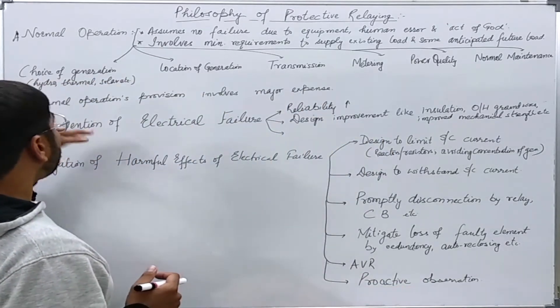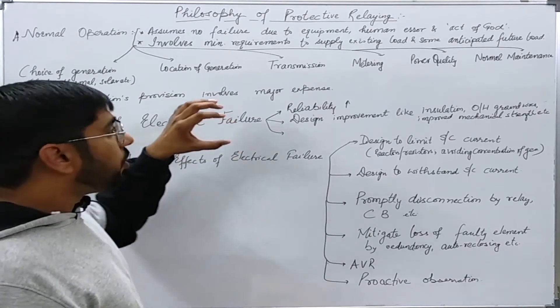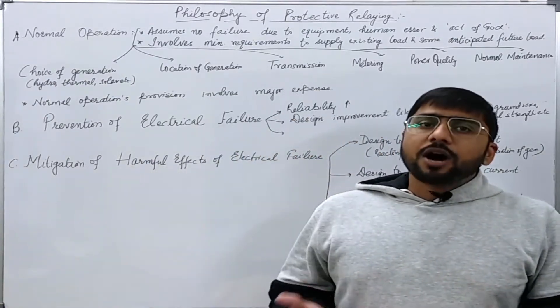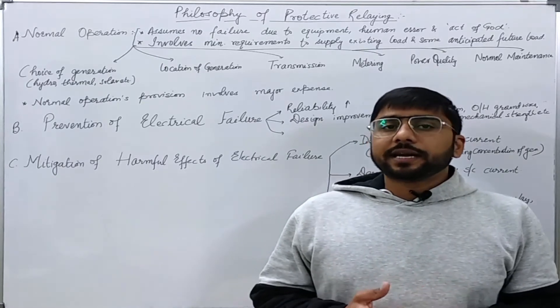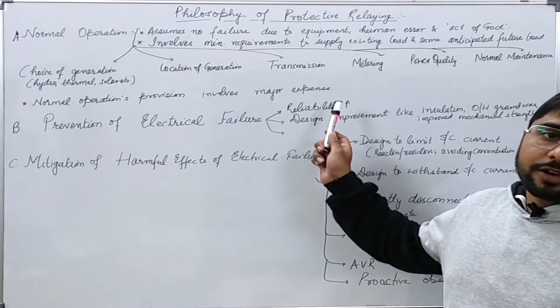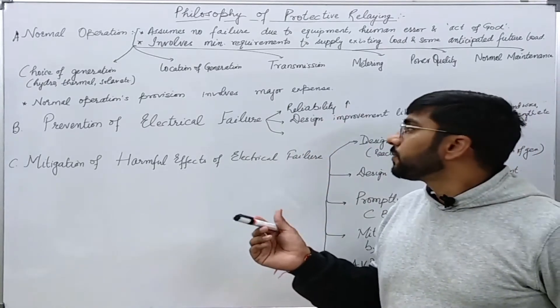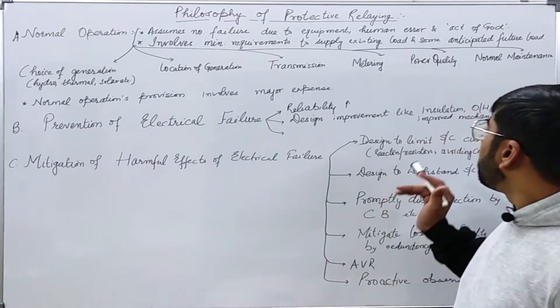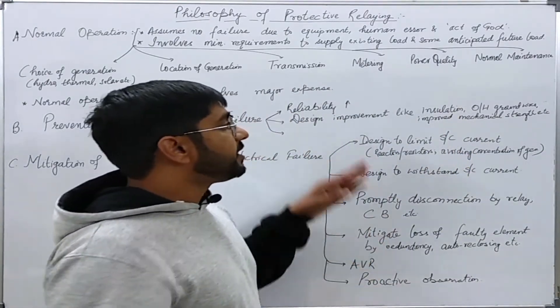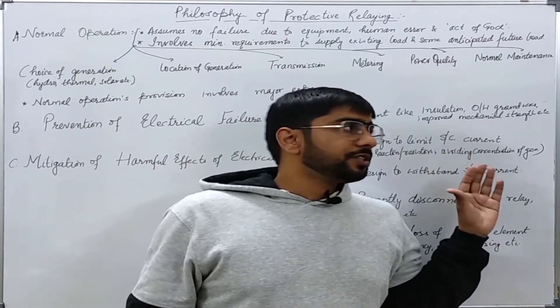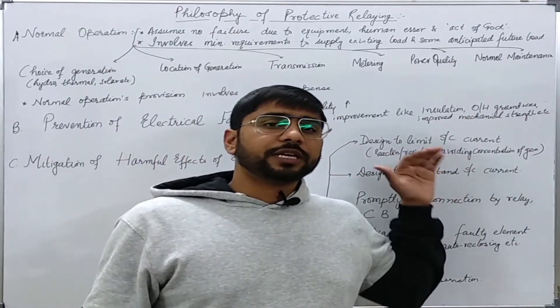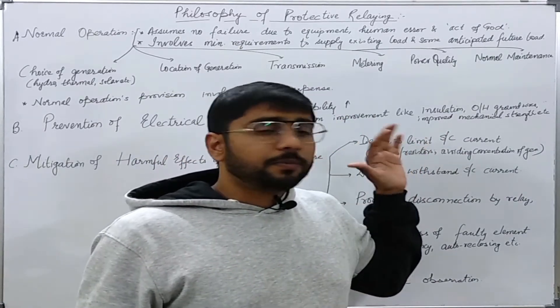Now there are two other aspects of a power system. We usually try to somehow prevent any electrical failure of the system. We do this by increasing the reliability using redundancy and improving the design of various equipment — like increasing the insulation level, improving insulation coordination, provision of overhead ground wires on transmission lines, and improved mechanical structure of the equipment.